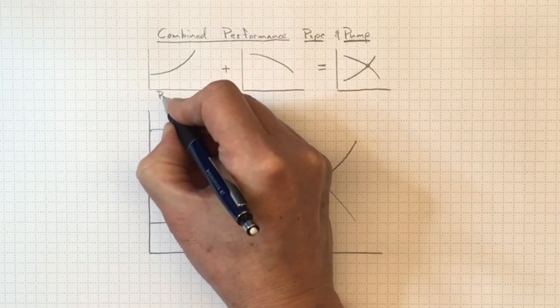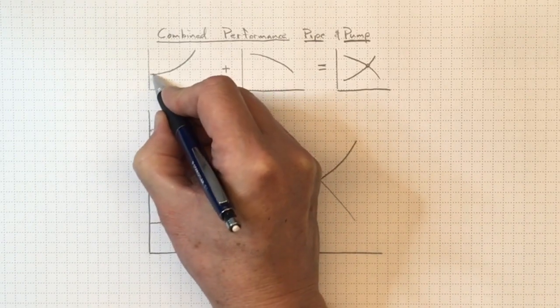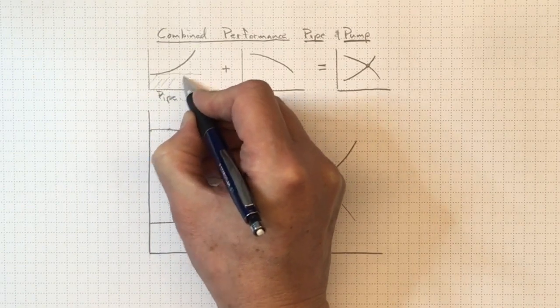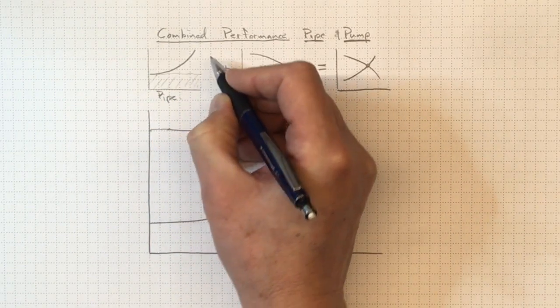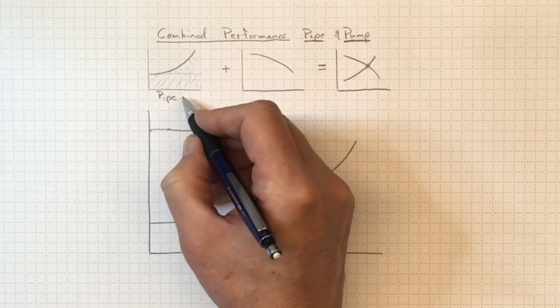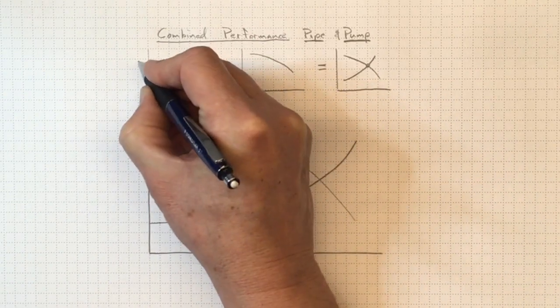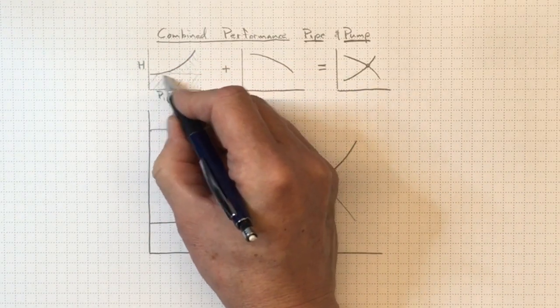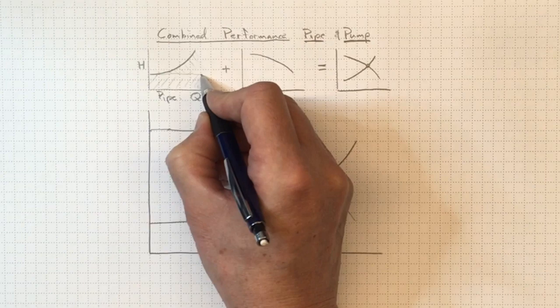The piping system will have a characteristic curve like this. It's got to have some elevation or pressure component that it's overcoming to do useful work, and then there's going to be an additional element of friction that's going to increase with increasing flow rate. So this is the head required to drive a particular amount of flow through a particular arrangement of piping.